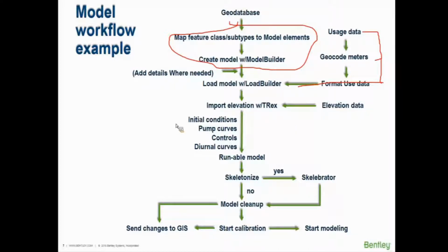And at that point, it becomes somewhat of the same task you've been going through the last few days. You would set up initial conditions, set up any pump curves, build your controls, enter in any diurnal curves. Maybe these come from somewhere else too, but you would be putting them into the model. And at that point, you have a model that you can run. And whether or not you choose to skeletonize your model and take out some of the complexity, take out some of the laterals that you don't need, you can choose to do that to lighten the load. But this would be kind of the happy path that you would follow to get a model that you can run and calibrate and actually start doing some really cool things with.